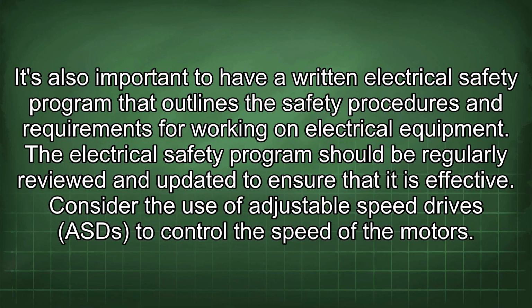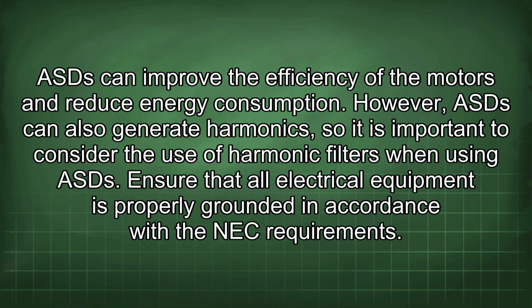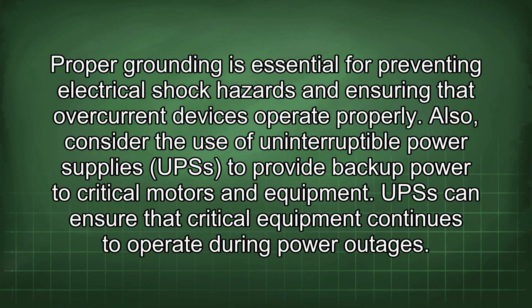Consider the use of adjustable speed drives (ASD) to control the speed of the motors. ASD can improve the efficiency of the motors and reduce energy consumption. However, ASD can also generate harmonics, so it is important to consider the use of harmonic filters when using ASD. Ensure that all electrical equipment is properly grounded in accordance with the NEC requirements. Proper grounding is essential for preventing electrical shock hazards and ensuring that overcurrent devices operate properly. Also, consider the use of uninterruptible power supplies (UPS) to provide backup power to critical motors and equipment. UPS can ensure that critical equipment continues to operate during power outages.